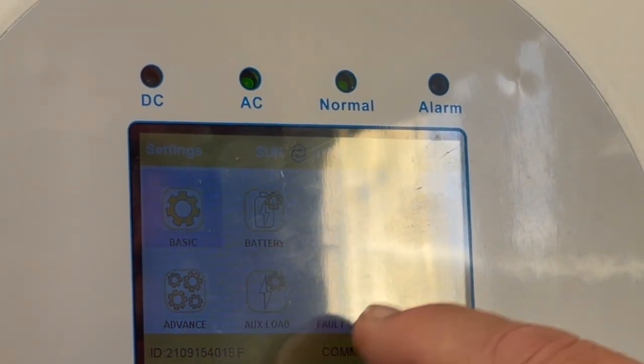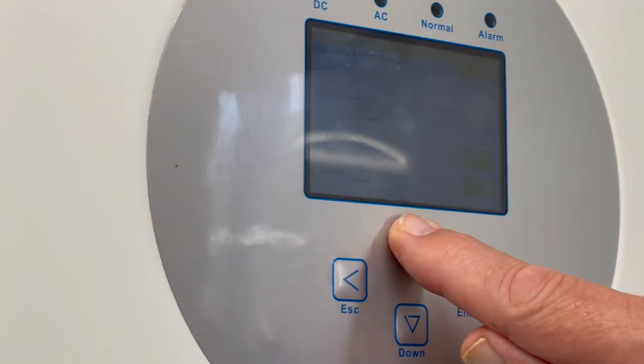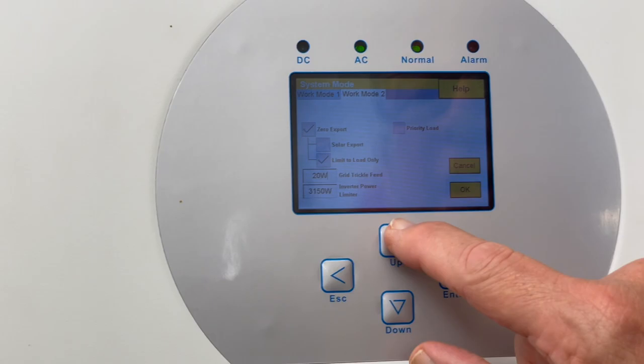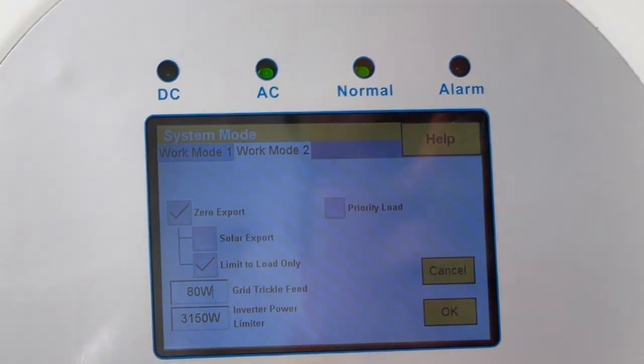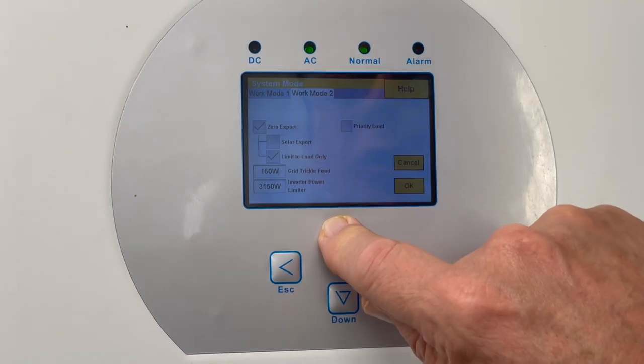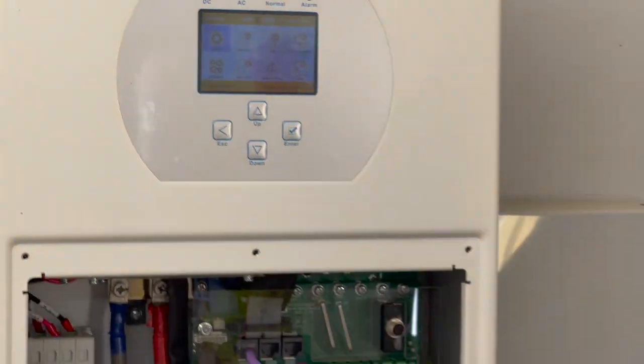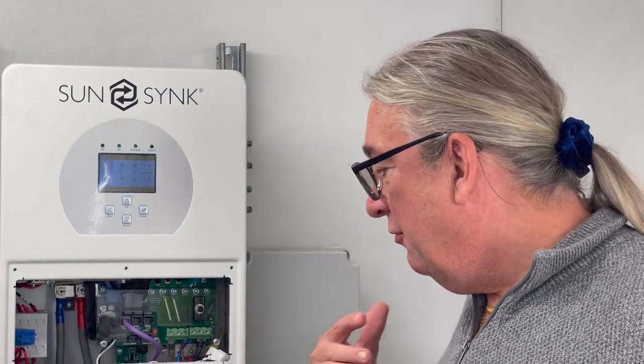And if I go on to the inverter system mode, I look here and in fact the inverter power limiter is actually set. So I can increase the inverter power limiter - the trickle feed. Because we're running off a generator, I'm going to take that up a little bit. We're not going to be exporting as such, so I'm just going to take that up to quite a high level. This will prevent absolutely anything going back onto the generator. So I've taken the grid feed level quite high on the input, because it's just a generator on the grid side. That's a trickle feed, because you're always going to have a feed - that's the whole point of using the generator. So there's always a feed in, we're never going to export ever. There's no AC coupling, it's just purely feed. And the output is on the load side, so that can be as high as you like - it doesn't matter.